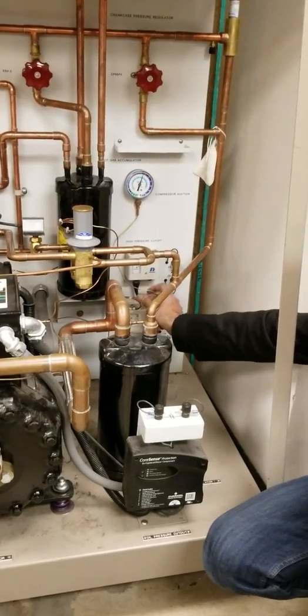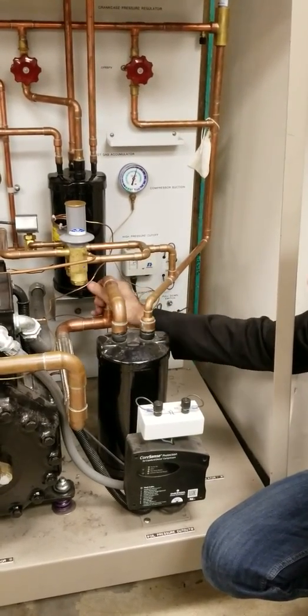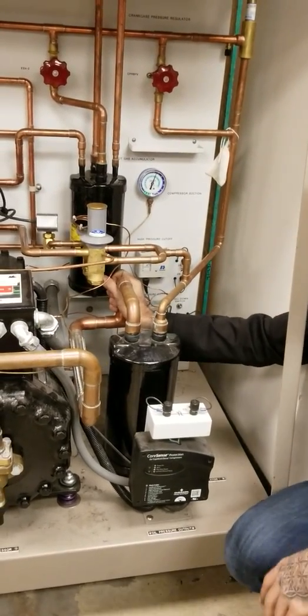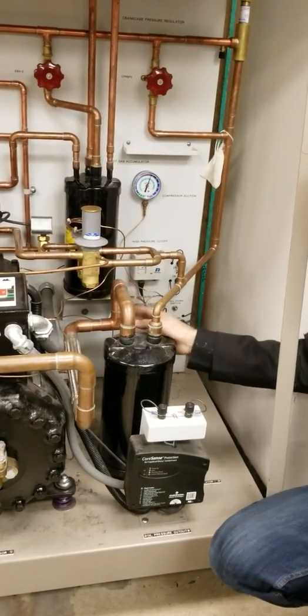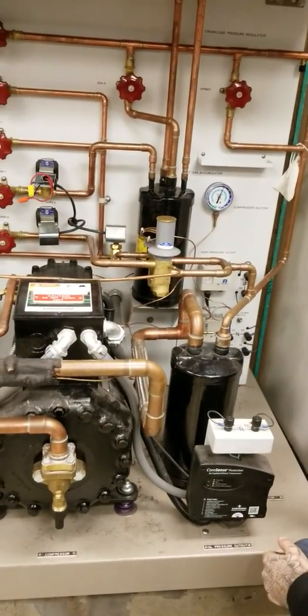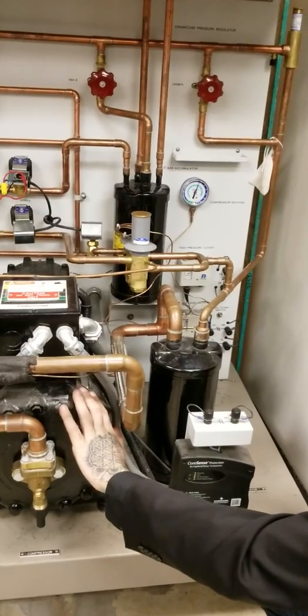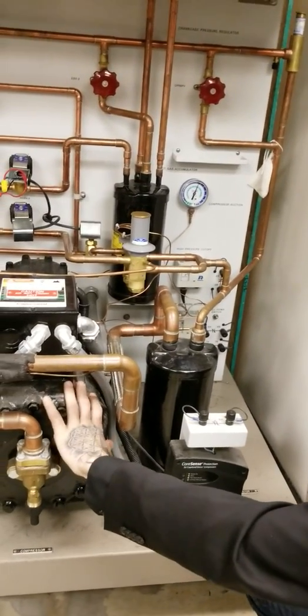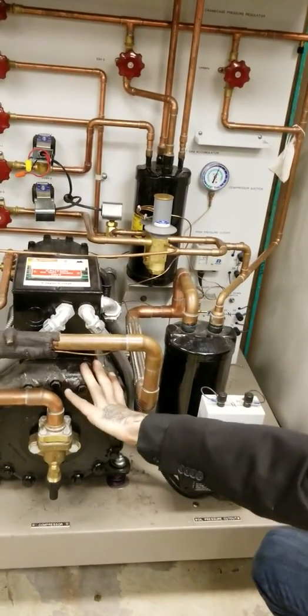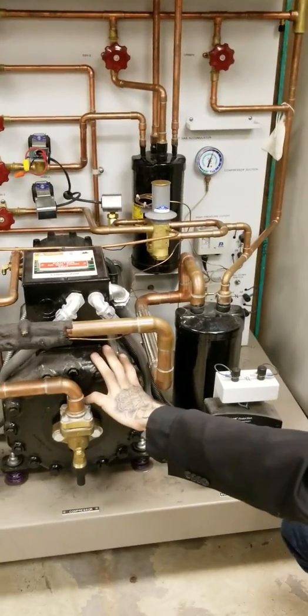Then you have a low pressure gauge tapped in so we could read our low pressure, and you have a crankcase heater that's going to keep this thing warm to prevent refrigerant migration, and make sure it's superheated vapor coming back and we're not taking any liquid.